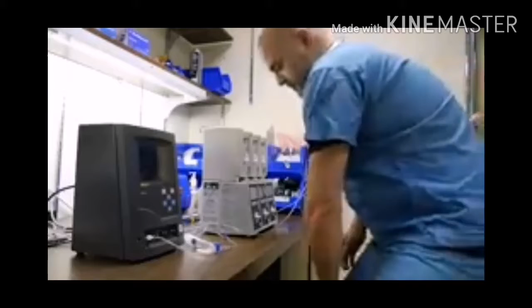Hi, my name is Sławian Angelov and I'm a biomedical equipment technician. The IDA5 is really accurate and fast. We use Hospira infusion pumps. Before we used the IDA5, we didn't have any idea what the percentage of error was. And now with the analyzer, it's way easier to find the exact numbers. You can precisely see what the volume, the flow, and the pressure are. And then you know if the pump works right or not.